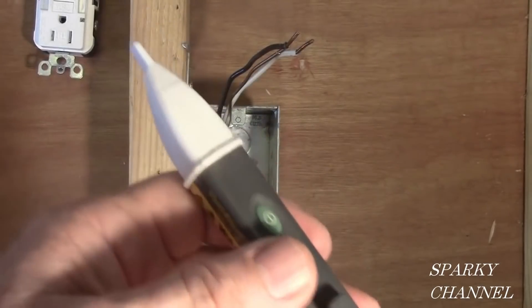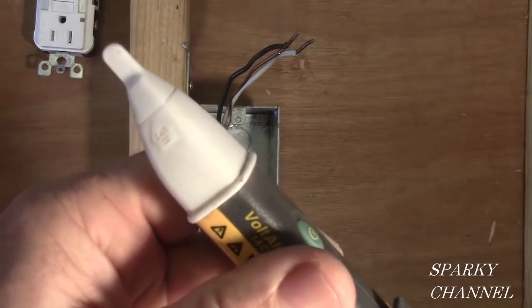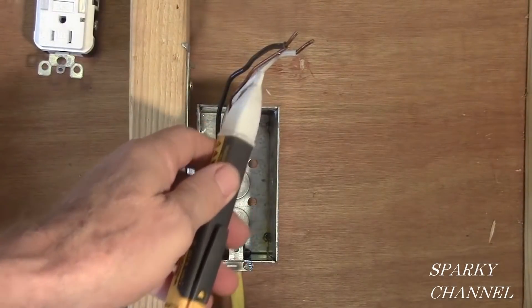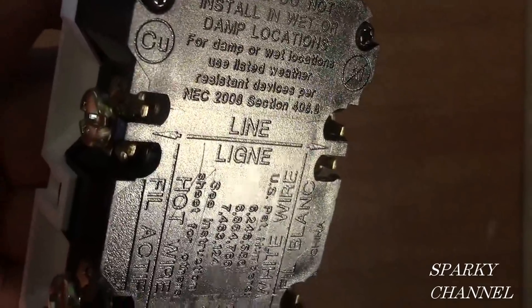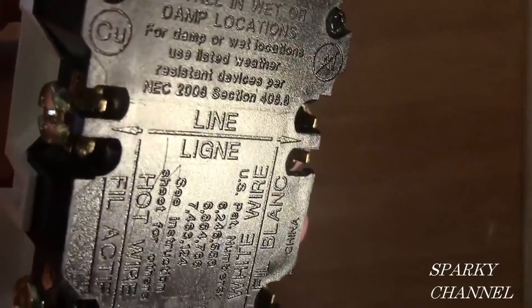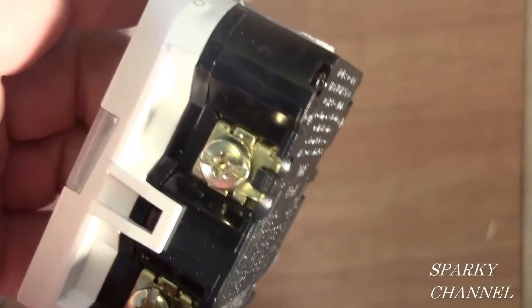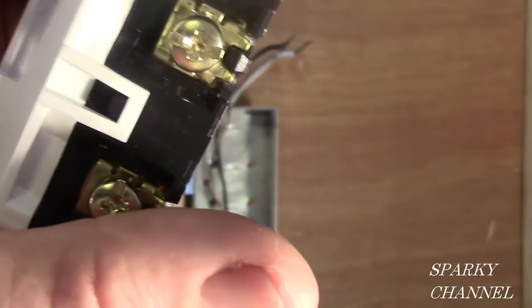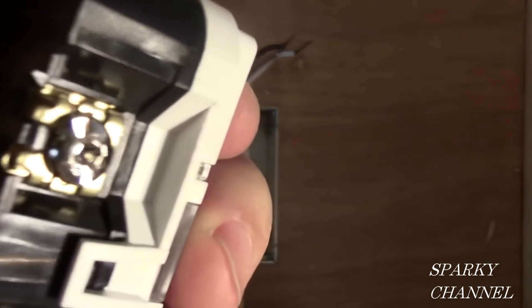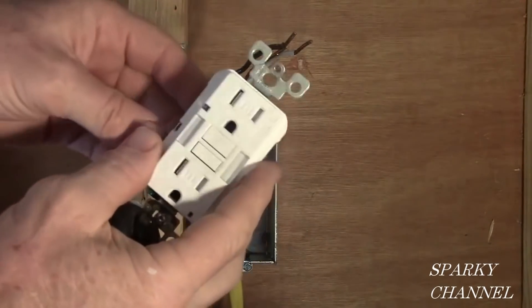Even though I've turned the circuit breaker off, I'm going to use my Fluke voltage detector to double check and make sure the electricity is off. Now I'm going to hook the hot black wire and the neutral wire to the line of the ground fault circuit interrupter. The black wire is going to go to this bronze screw and the white wire is going to go to the silver screw. Remember, we've double checked to make sure the electricity is off.